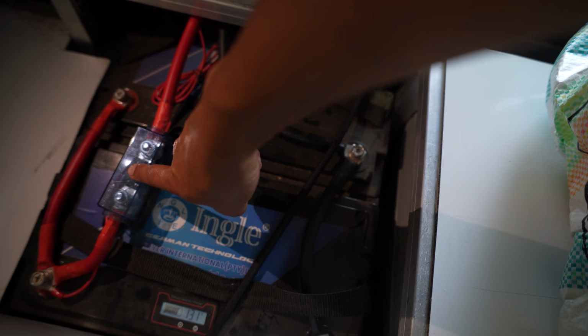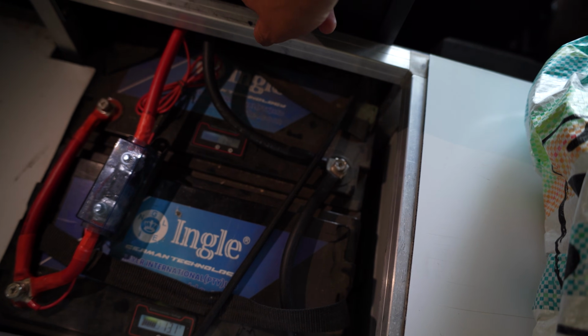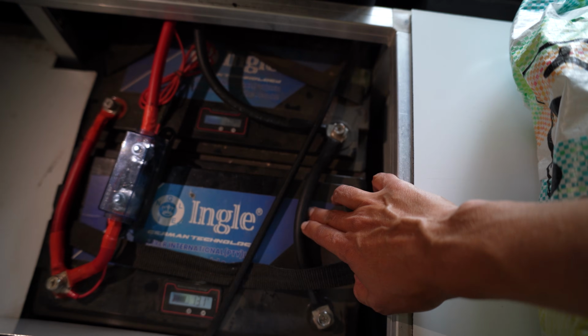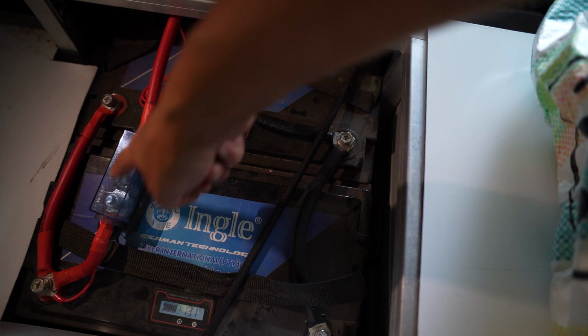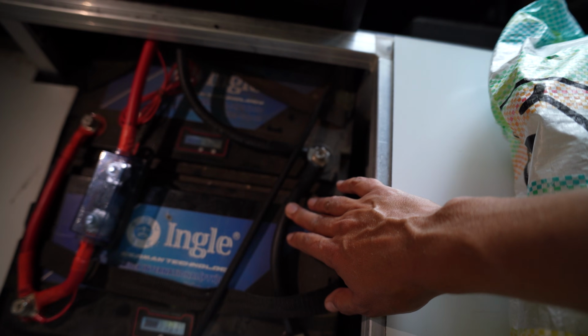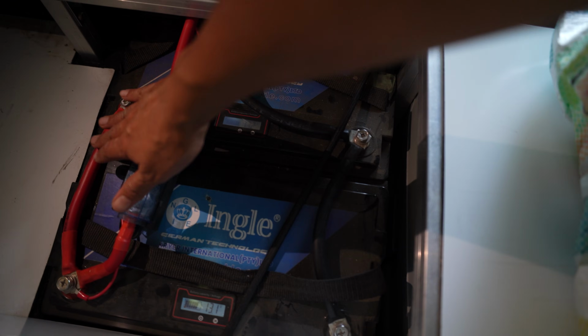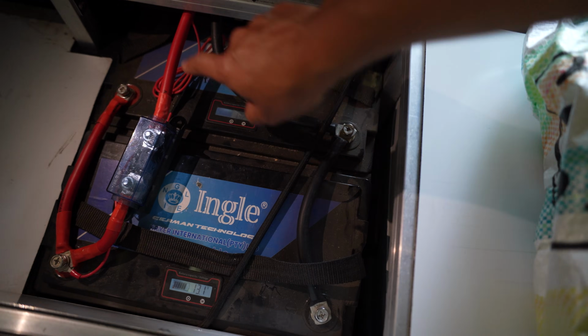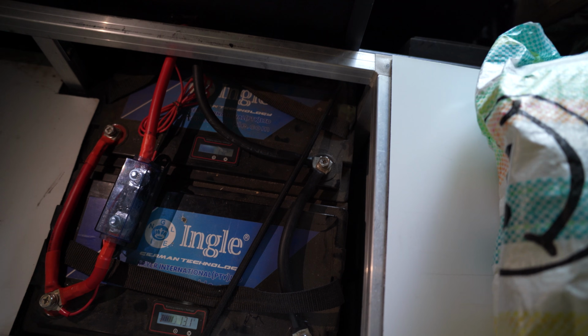The fuse is closest to the source so that it quickly burns out before you can reach anything else. And these wires between the batteries, and these ones as well to the system, try and keep them the same length. So this same length as that, the whole thing the same length as the whole black wire to the bus bars.